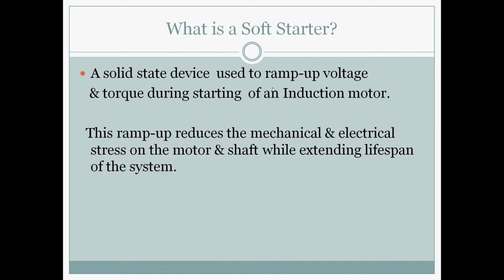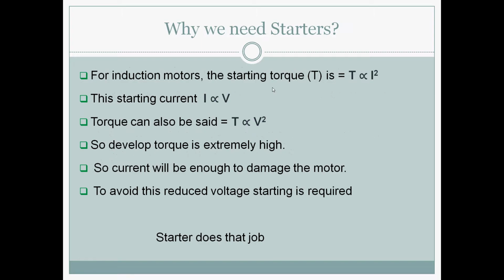What is a soft starter, first of all? It's a solid state device to ramp up the voltage and torque during starting of an induction motor. So the technology is different. Here starting and running is done by ramping up the voltage and current. It is increasing gradually. The ramp up reduces mechanical and electrical stress on the motor and shaft while extending the lifespan of the system.